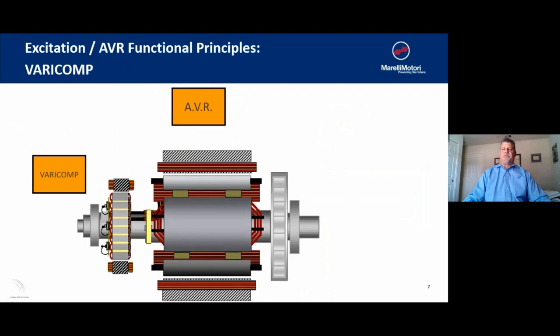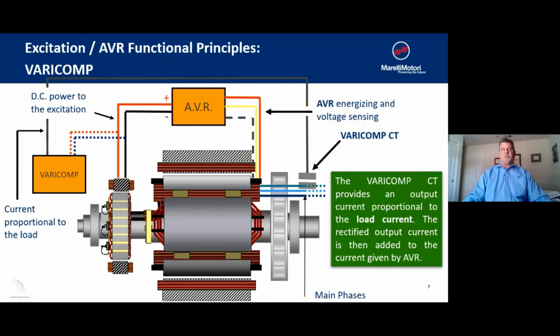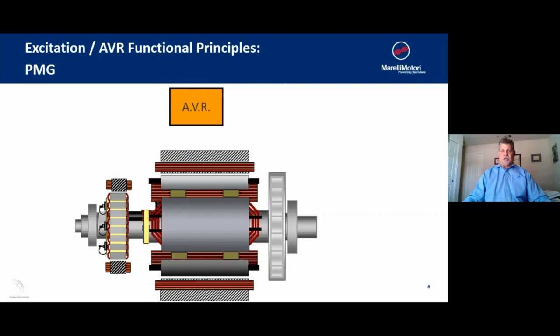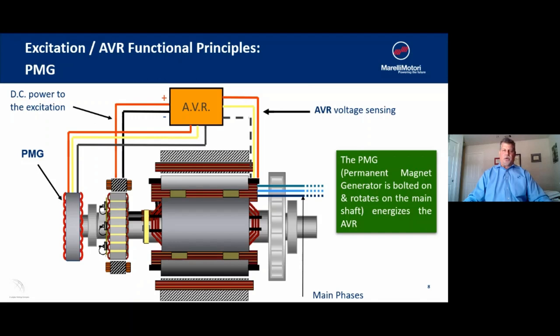We also use what's called a Varicomp device — for lack of a better term, an overboost system that uses a CT to sense the output current, feeds that back into the Varicomp, rectifies that signal, and adds it to the signal to the AVR. These devices are typically used when you have large AC motors connected to the unit. Last, permanent magnet generators bolt onto the end of the main rotor; because of their residual magnetism, they supply a very strong and clean signal directly to the AVR and are primarily used when you require 300% overload capability on the alternator.